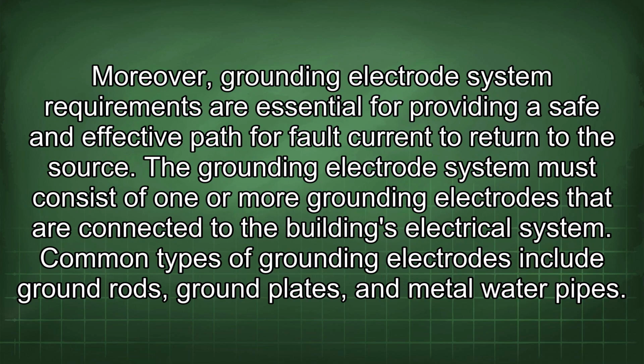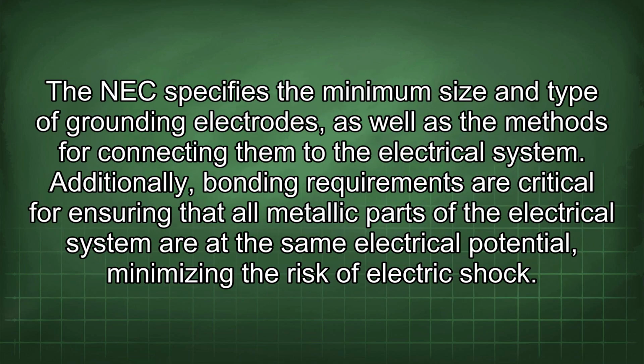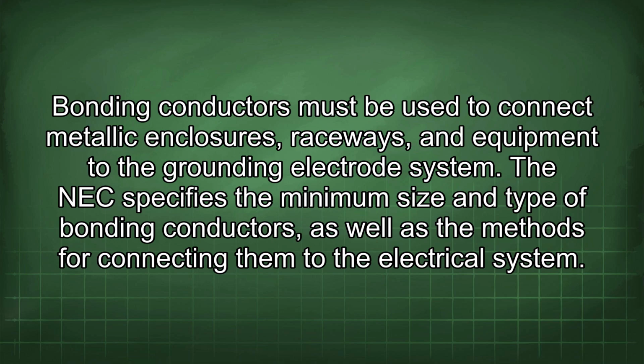Moreover, grounding electrode system requirements are essential for providing a safe and effective path for fault current to return to the source. The grounding electrode system must consist of one or more grounding electrodes that are connected to the building's electrical system. Common types of grounding electrodes include ground rods, ground plates, and metal water pipes. The NEC specifies the minimum size and type of grounding electrodes, as well as the methods for connecting them to the electrical system. Additionally, bonding requirements are critical for ensuring that all metallic parts of the electrical system are at the same electrical potential, minimizing the risk of electric shock. Bonding conductors must be used to connect metallic enclosures, raceways, and equipment to the grounding electrode system.